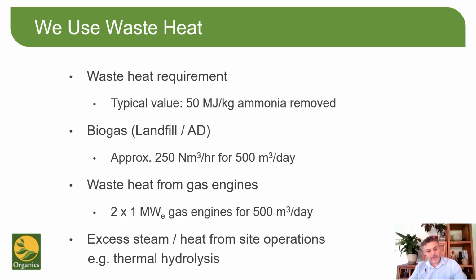If we are going to recover the ammonia rather than destroy it, then we can use a waste heat source to fuel the process from perhaps gas engines on site or spare steam from some other system on site. To give you an idea of the sort of heat load required, it takes about 50 megajoules per kilogram of ammonia removed. Or in terms of biogas, at say 60% methane, you would need around 250 cubic meters an hour of biogas to treat around 500 cubic meters a day of wastewater and destroy the ammonia produced.